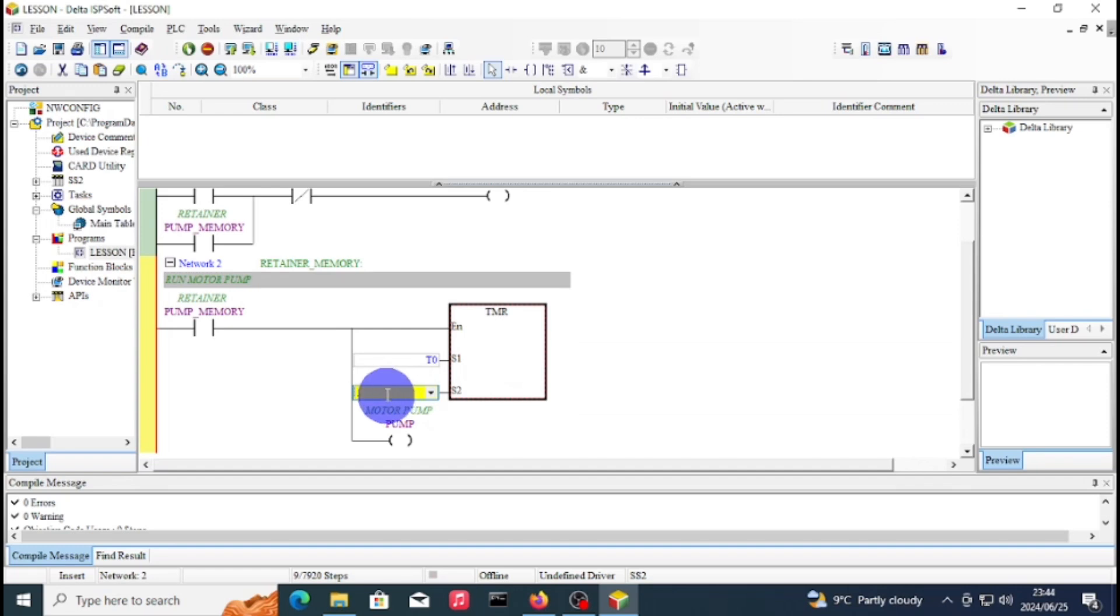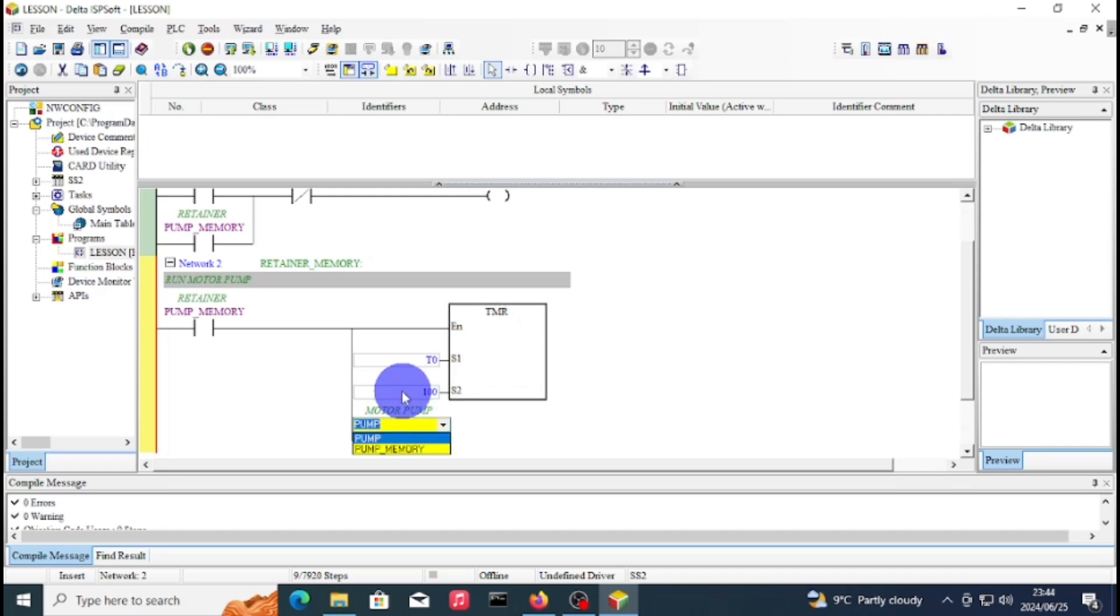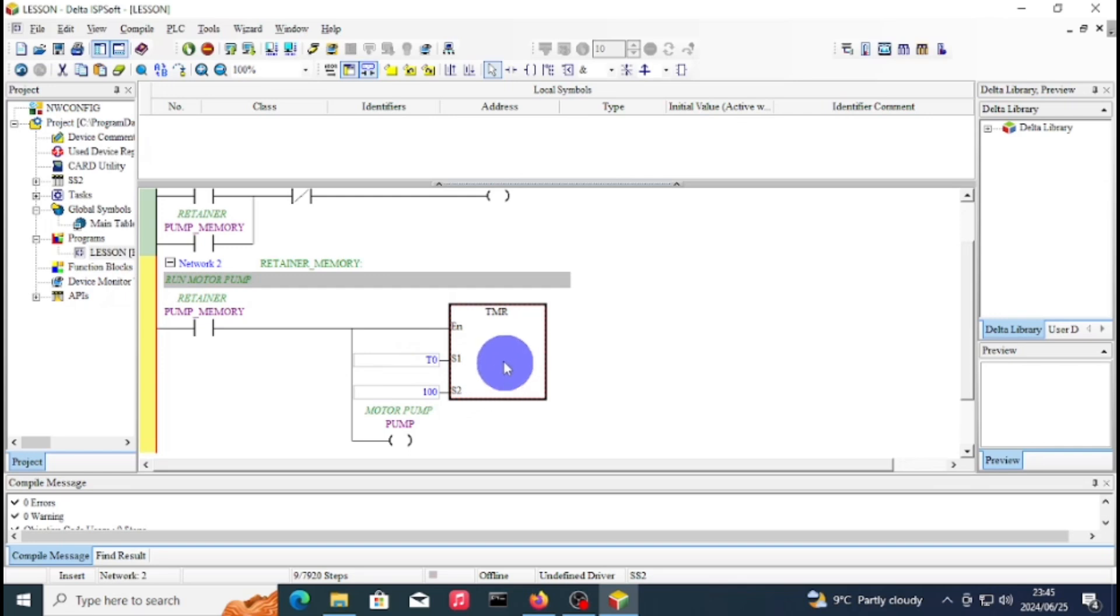I want to add 10 seconds. Remember on the Delta PLC you don't just say 10 seconds because of the bit. You say 100 if you want to add 10 seconds, because it's whatever number you add times 100 milliseconds. So if you want 10 seconds you write 100, then times 100 milliseconds, then it will give you 10 seconds.